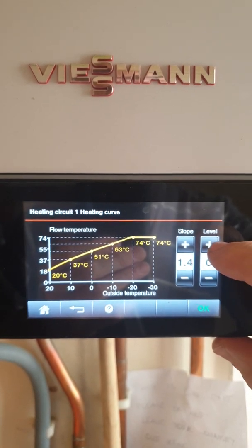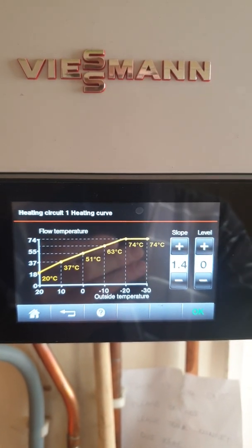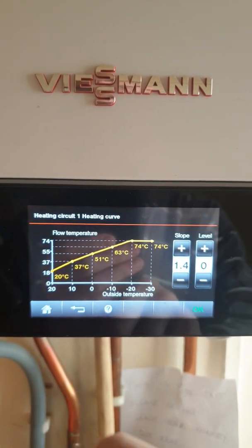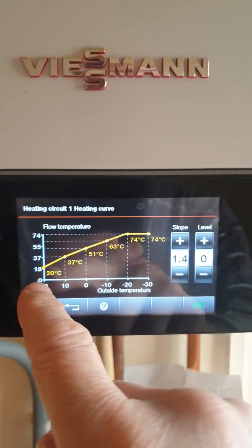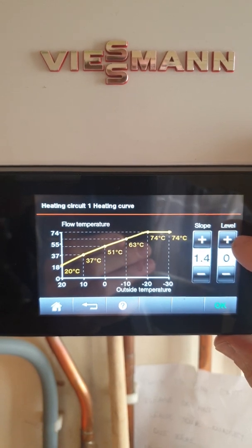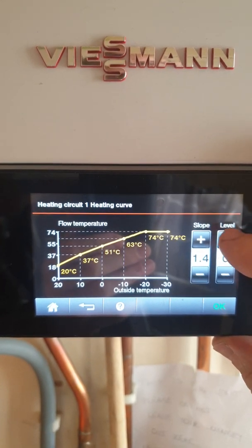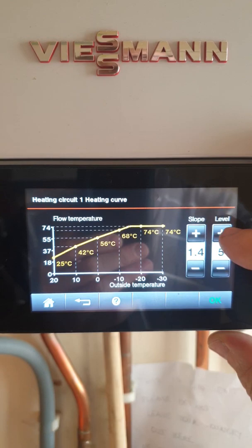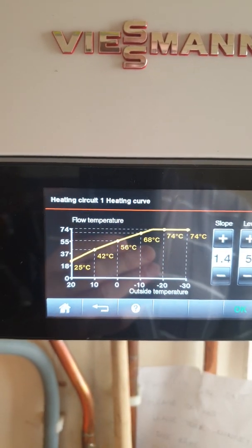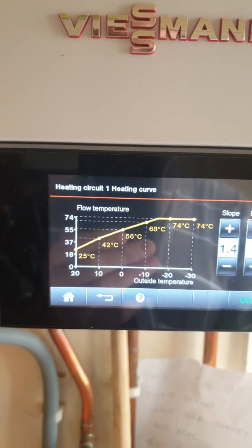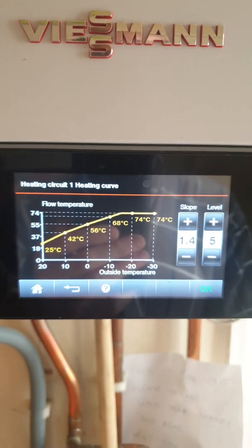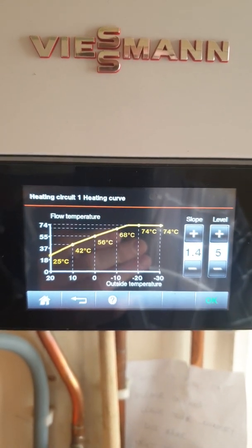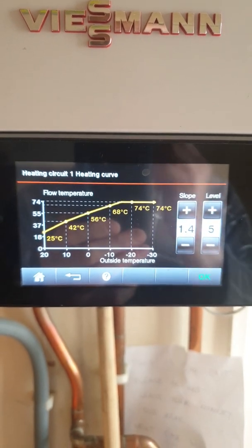Now the level — when you adjust temperature — at the moment I'm set for 20 degrees room temperature, so it's showing that curve. But if I set the temperature, say I wanted to heat to 25, it can go up on my curve. That's now looking to give me a room temperature of 25 degrees. And I've adjusted the level manually here, rather than on the temperature selection side of the boiler.